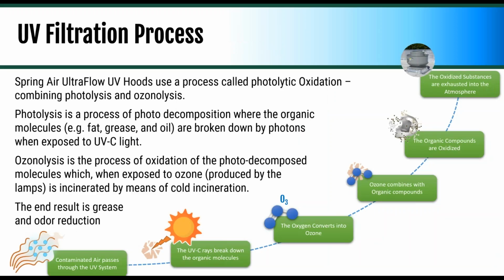But just to go through the UV filtration process, you heard it in the video, photolytic oxidation. Basically, what happens is the contaminated grease coming off the appliances with all of those aerosolized pollutants comes through the UV system, and that's where UVC is the first step. The bulbs emit a particular wavelength. I think it's 254 nanometer maybe, but it's UVC, and that actually breaks down the organic molecules. That does the heavy lifting for a lot of the removing of the grease and odor particulate. But then as a byproduct of the UVC creation, oxygen is actually converted into ozone. That ozone actually combines with the remnants of the organic compounds and oxidizes them.